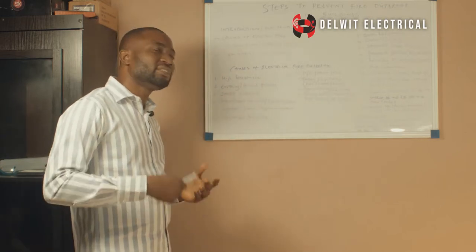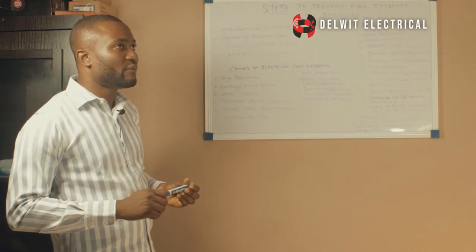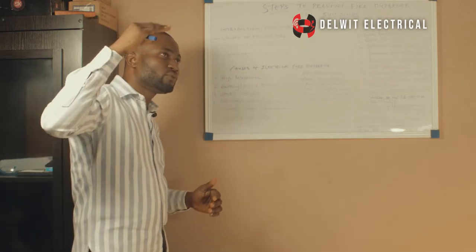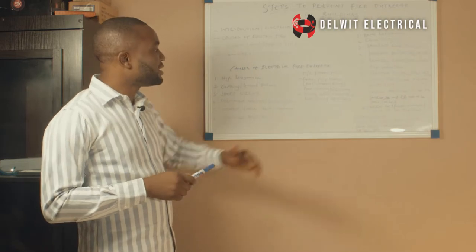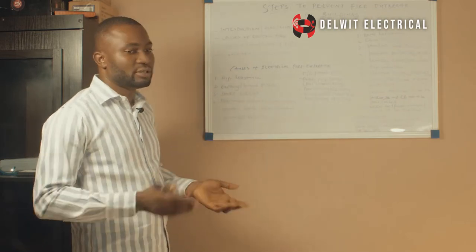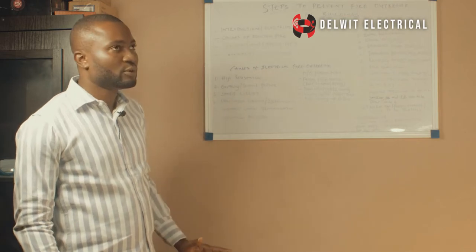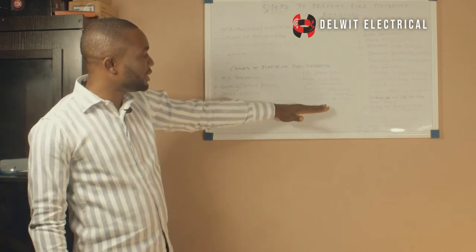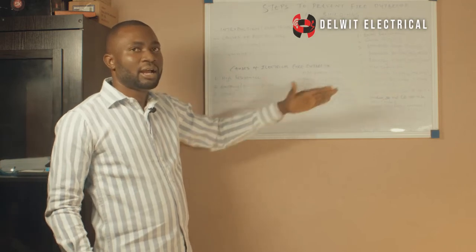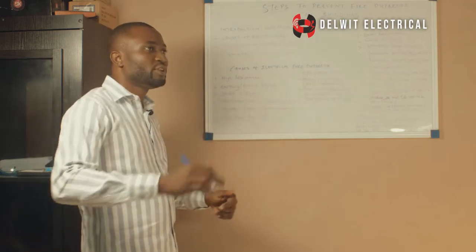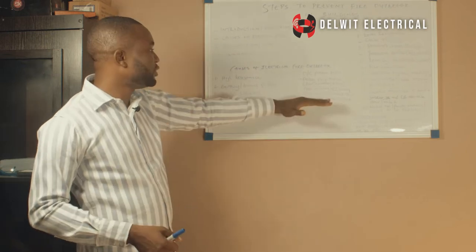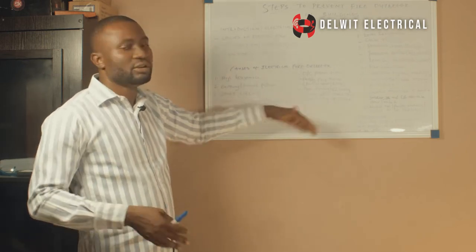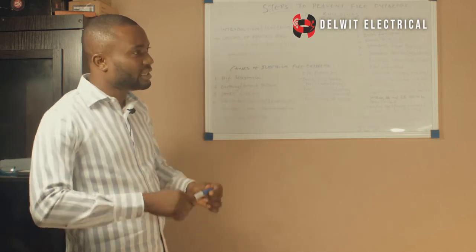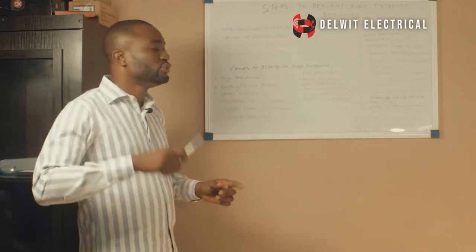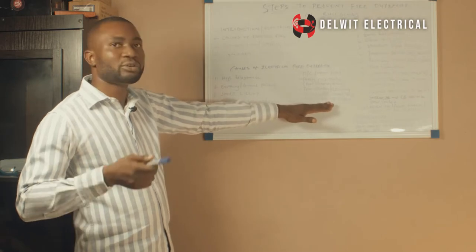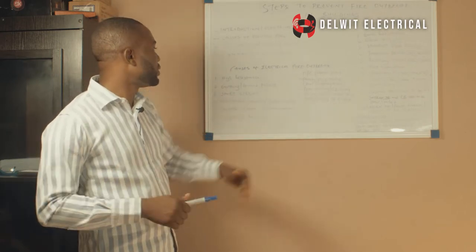Then, rather than have rodents eating up your cables, you will discover that in buildings where you have access to the rooftop and half conduit is used, when they eat up the cable, you might be fortunate that the particular cable they eat does not function. But you might be unfortunate that they eat up the red side and also the black. And along the line, when it's moving, it will bridge both of them. When they bridge both of them, the live and neutral bridging, you know what that is. So it's advisable that in this modern connection era, you ensure that you do full conduit, and that will eliminate every aspect of rodents eating up your cable.